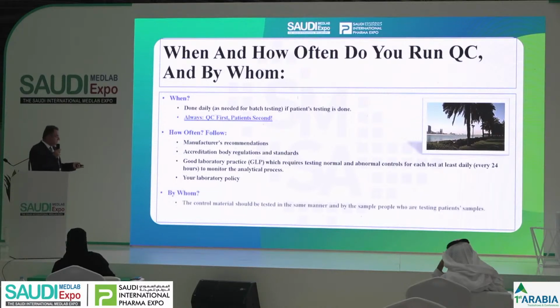By whom? Those who are involved in doing patient testing, they need to be involved in doing QC also. You cannot have just one individual running the QC and the rest of the staff running patients. They have to be involved in doing the QC also, okay?